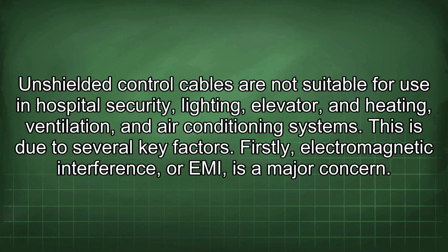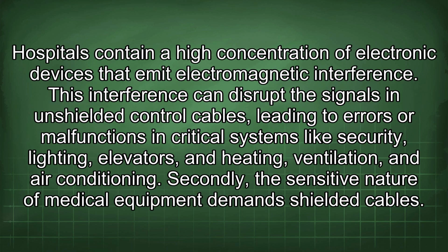Unshielded control cables are not suitable for use in hospital security, lighting, elevator, and heating, ventilation, and air conditioning systems. This is due to several key factors. Firstly, electromagnetic interference, or EMI, is a major concern. Hospitals contain a high concentration of electronic devices that emit electromagnetic interference. This interference can disrupt the signals in unshielded control cables, leading to errors or malfunctions in critical systems like security, lighting, elevators, and heating, ventilation, and air conditioning.